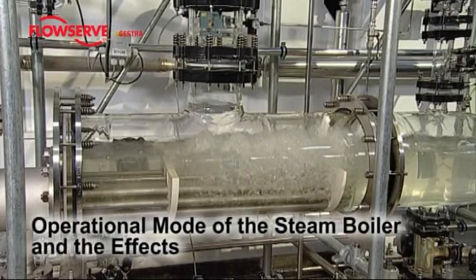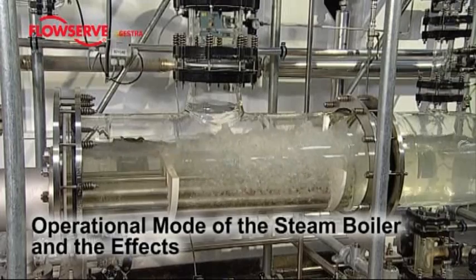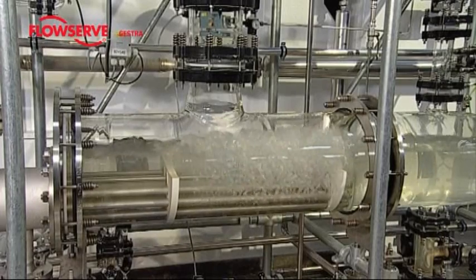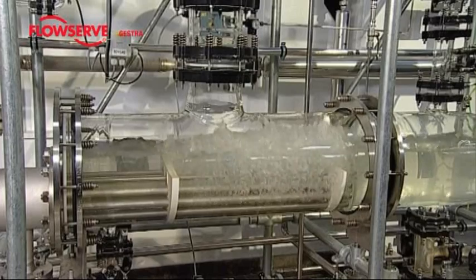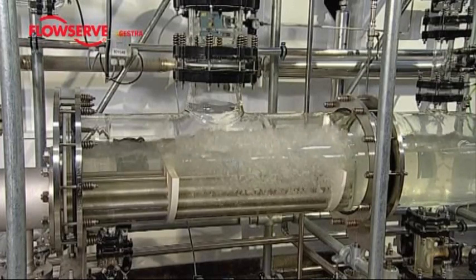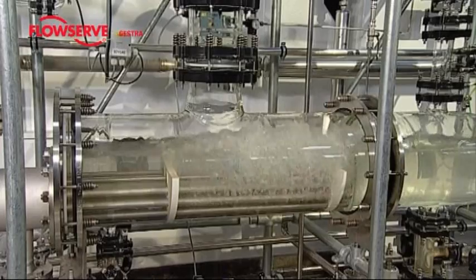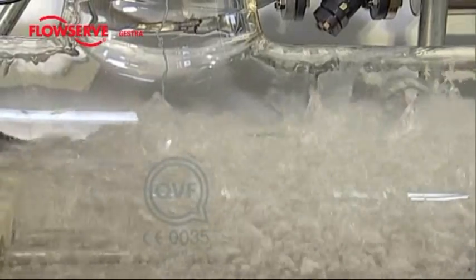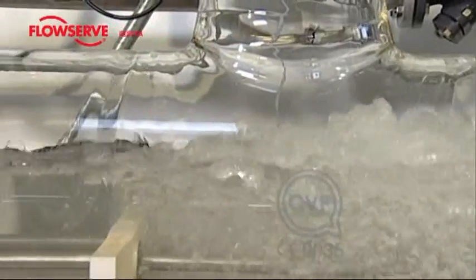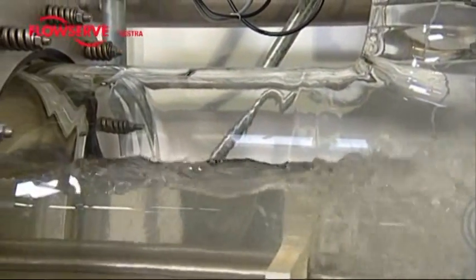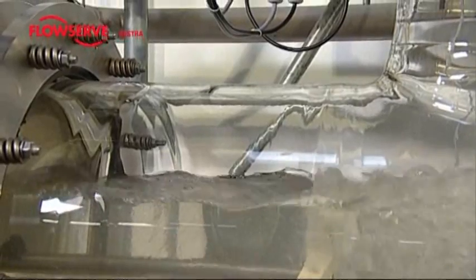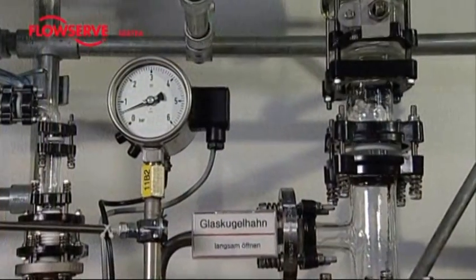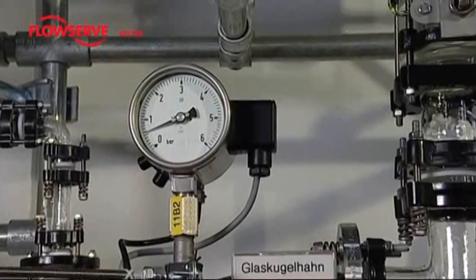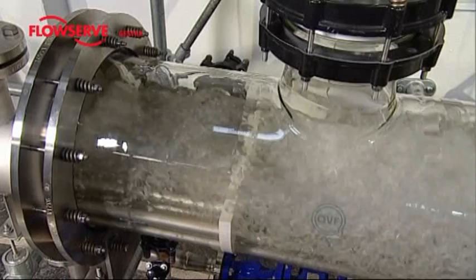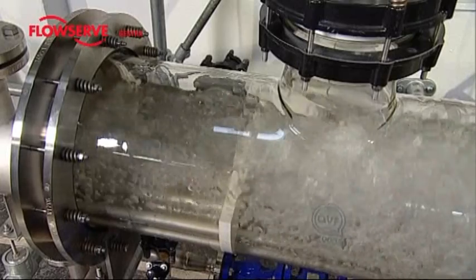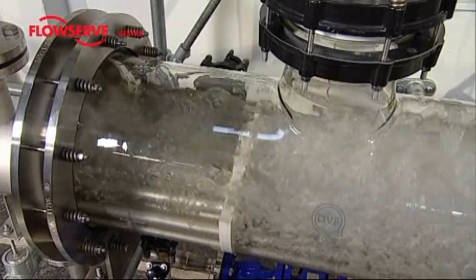We will now conduct a test by increasing the level of the water in the steam boiler from 60 to 67%. Slowly, the feed water valve opens, and feed water with a lower temperature than that of the boiler water enters the steam boiler. This now mixes with the boiler water. Because the temperature of the mixture lies below the boiling point, there's no longer any formation of steam bubbles in this area. The steam boiler lacks performance, and a glance at the pressure gauge tells us that the working pressure is sinking. To counteract this power dip, the feed water in steam boiler plants is routed through the economizer, where it is preheated through the hot gases of the burner exhaust.